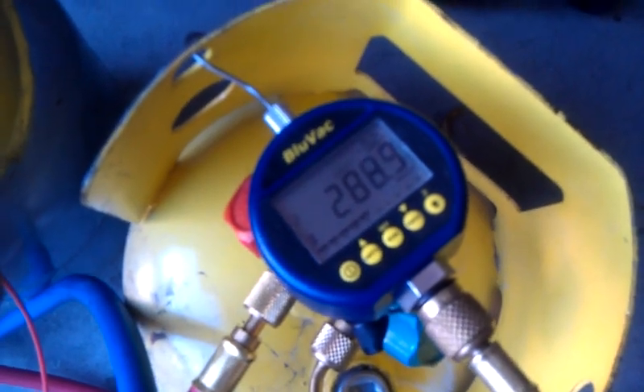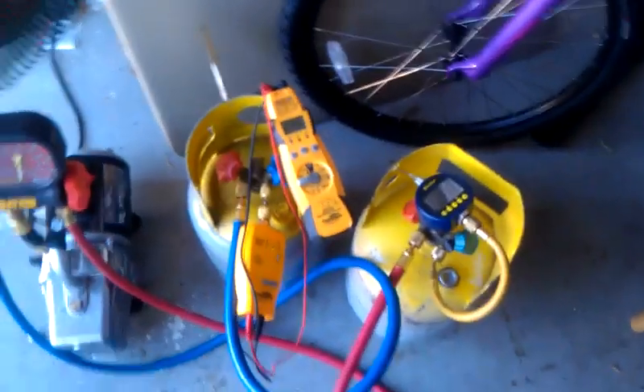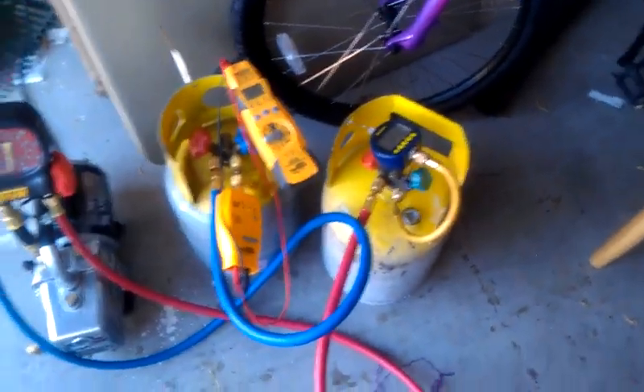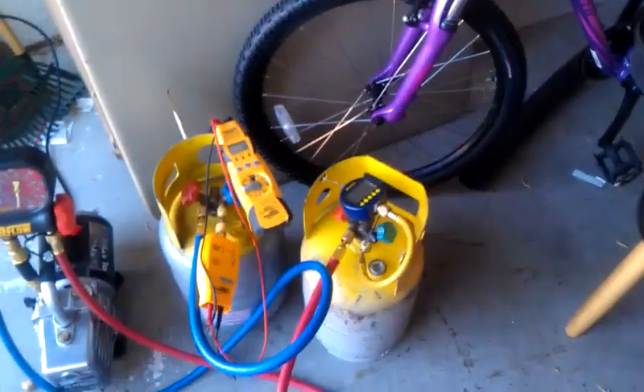But it's just something to note that there is about a 50 micron discrepancy there, which really, 50 microns, in the grander scheme of things, I'm not sure how much difference that truly makes, but it could make some difference. I know some of these startup and remodel jobs, some of these guys are getting pretty particular about where they want that stuff to be at before they hit the go button.